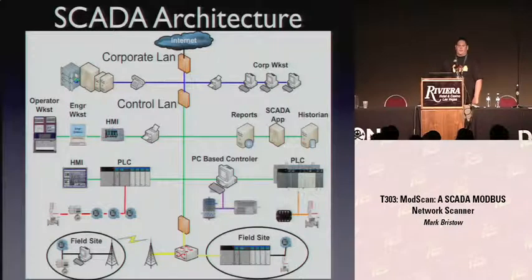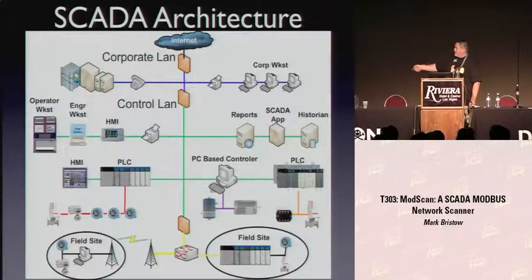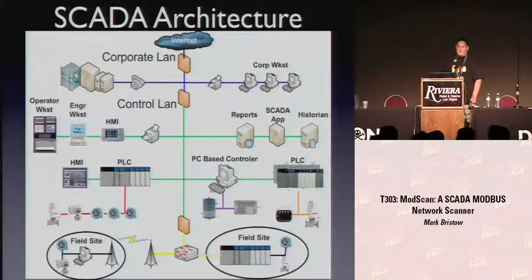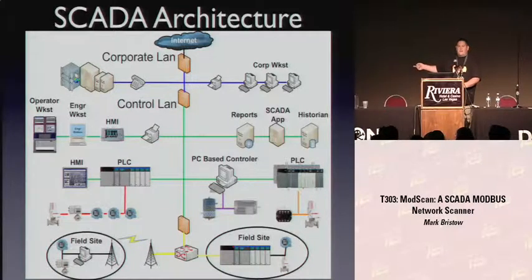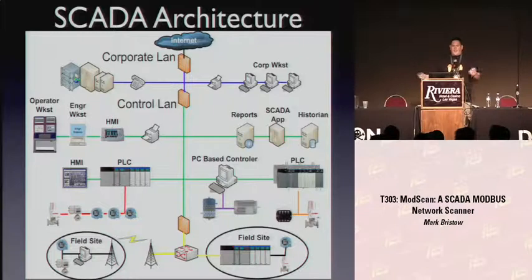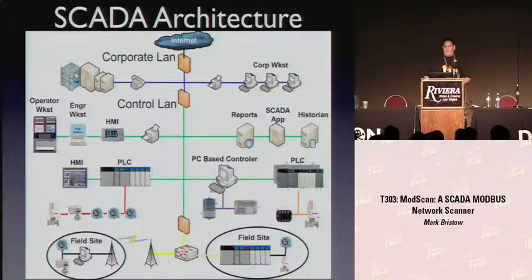This here is kind of what SCADA looks like conceptually from my experience with clients. You typically have a big corporate network, some type of control network, some field sites at the bottom, and a whole bunch of stuff running in between. You've got specialty devices, regular servers, these big things called PLCs which are the brains of the operation, along with the SCADA application controller. Each color line on this slide represents a different protocol. SCADA networks today are just a big hodgepodge - TCP/IP, Modbus serial, Modbus TCP, DNP3, all kinds of stuff.